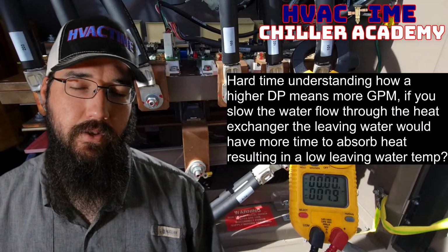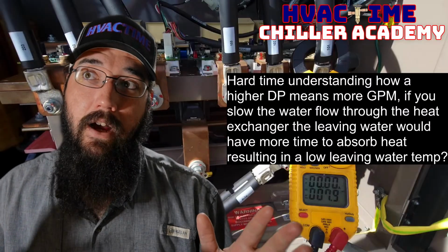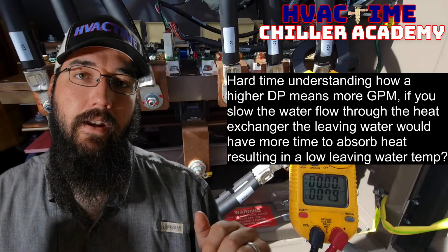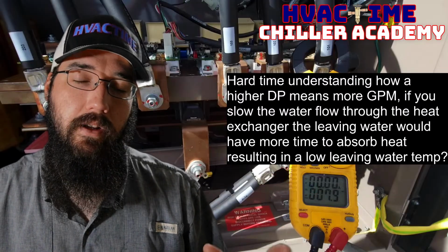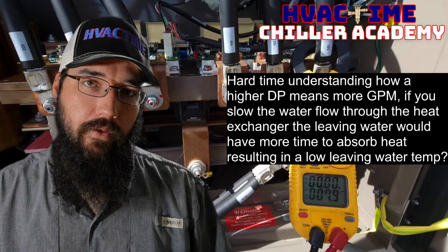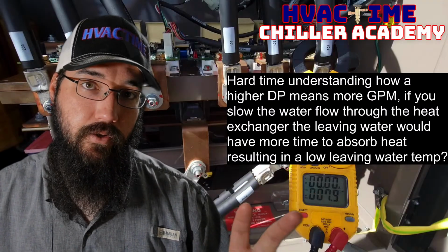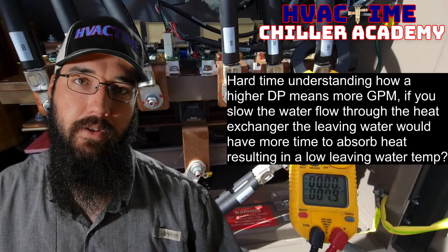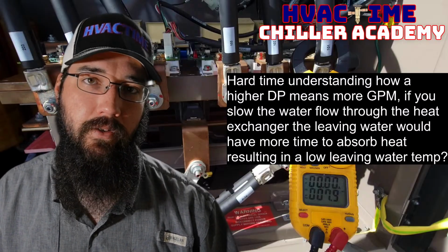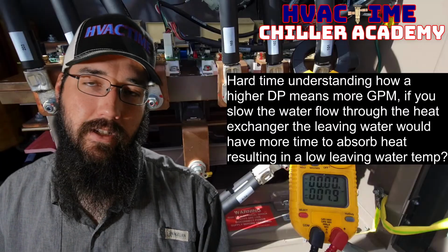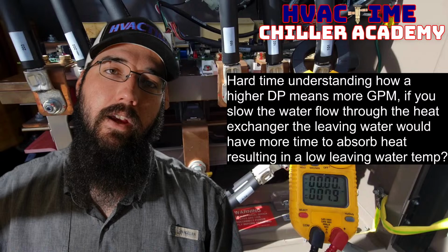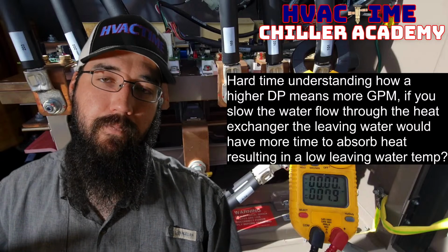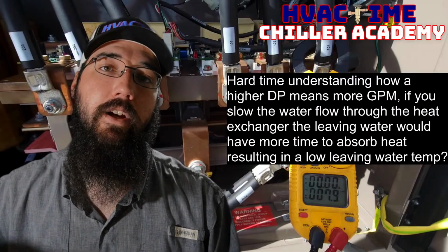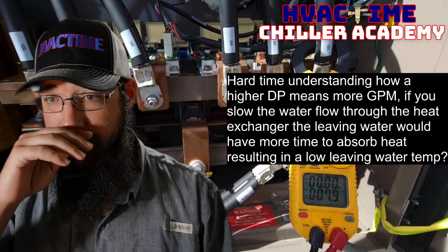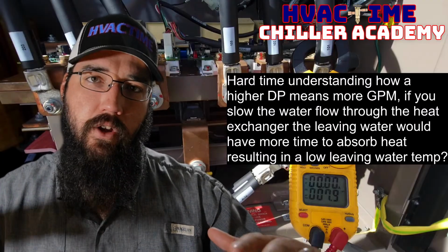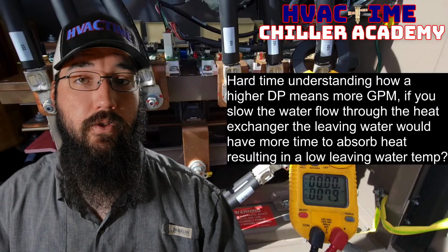So getting back to the pressure side of this, there is a difference between how we rate a heat exchanger and how we rate, say, a valve, or like a balancing valve. So with a valve, if we create a pressure differential across there, or a strainer is another example of this, the more differential across that component, the less flow that component is actually letting through it. Whereas with a heat exchanger, if we want more flow, we're trying to increase the differential. Now, more flow does reduce the temperature difference across there.